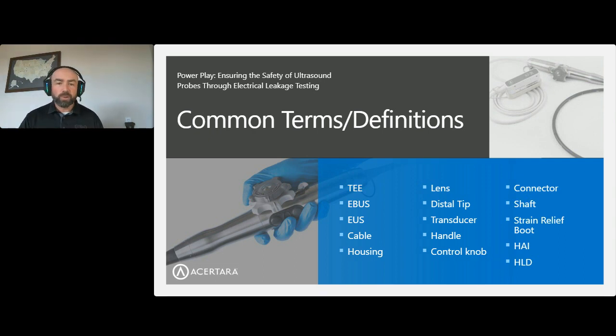And so if you look at one of these probes, particularly a TEE probe, in a very small space, maybe half an inch by half an inch, you can have as many as 2,500 elements. So these elements are very, very small. Each of those elements makes up the array, and each one is effectively its own small crystal transmitter, right? And they all work on the piezoelectric effect, which is the ultrasound system will transmit an electrical signal.